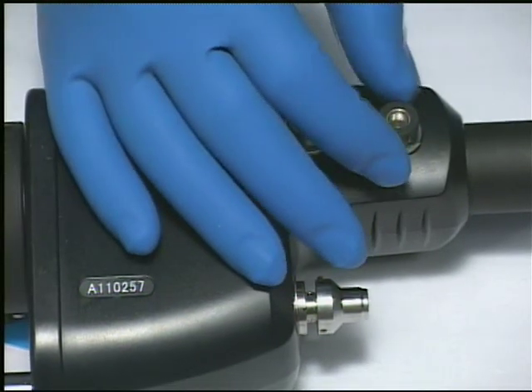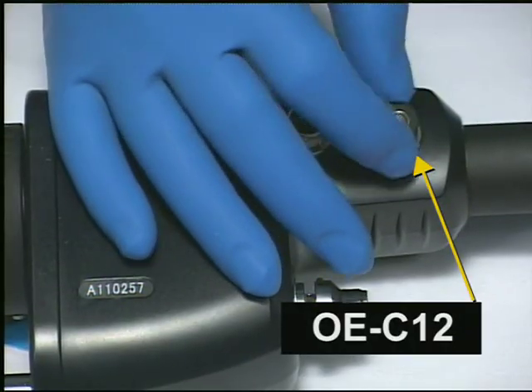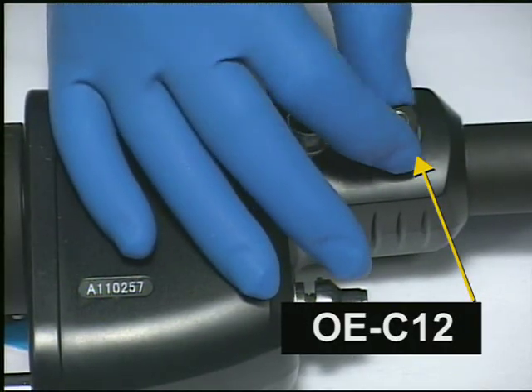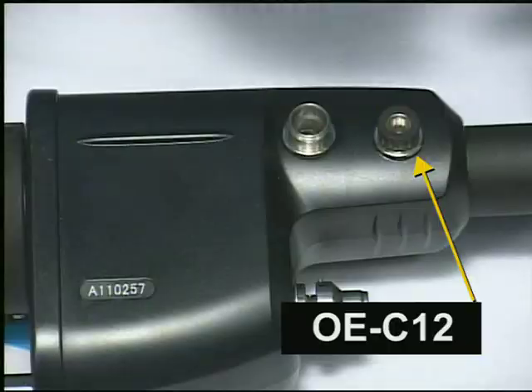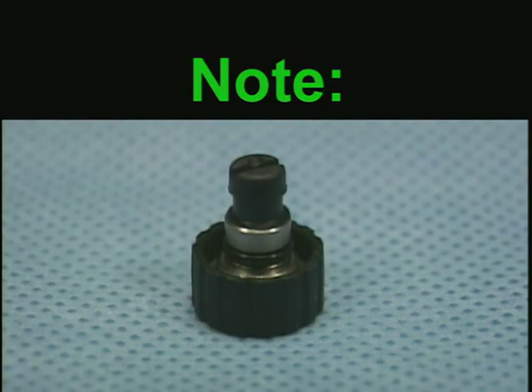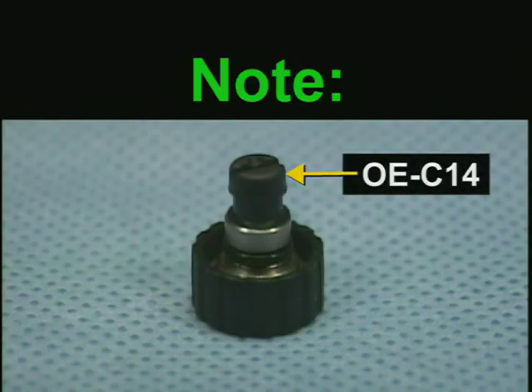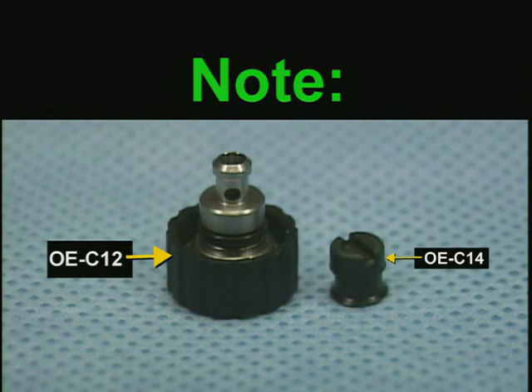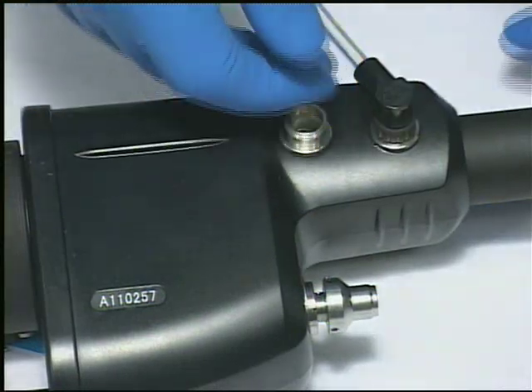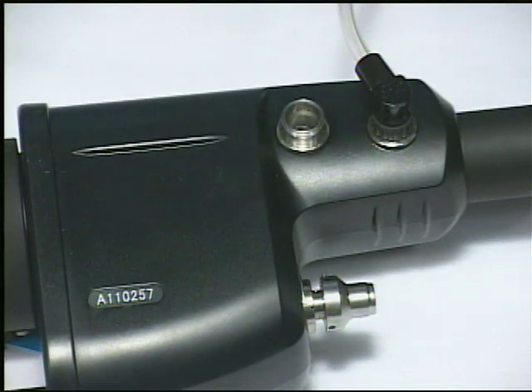Reattach the water jet check valve adapter OEC12 to the PVE connector on the endoscope. Note that during the cleaning process, it is recommended that the rubber check valve OEC14 be removed from the base of the OEC12 check valve adapter prior to reattaching it to the scope. This will allow for unrestricted flow of solution into the small water jet channel.